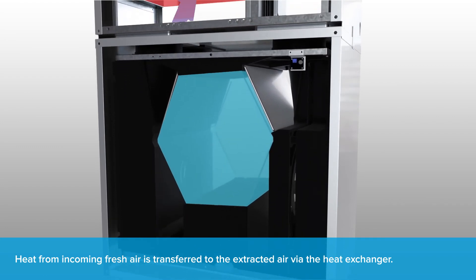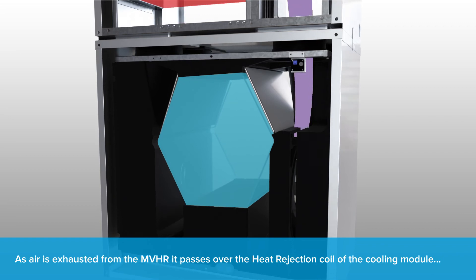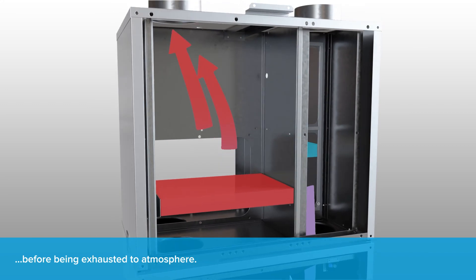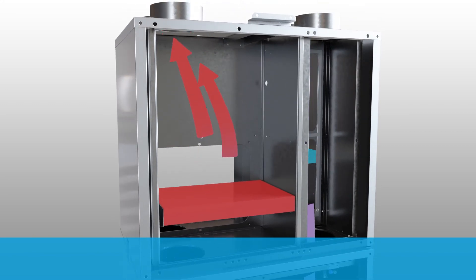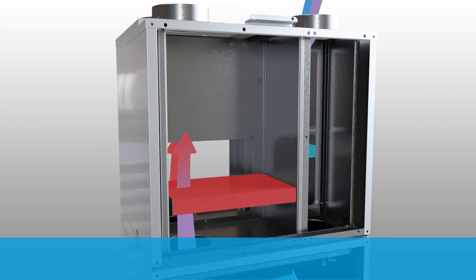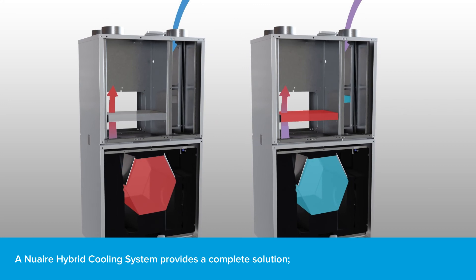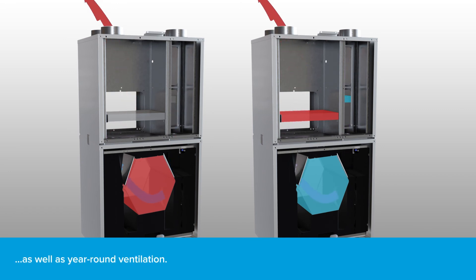Air is extracted from wet rooms, and heat from the incoming fresh air is transferred to the extracted air via the heat exchanger. As air is exhausted from the MVHR it passes over the heat rejection coil of the cooling module before being exhausted to atmosphere. A Nuaire Hybrid Cooling System provides a complete solution: high efficiency heat recovery in winter, cooling to mitigate overheating in summer, and year-round ventilation.